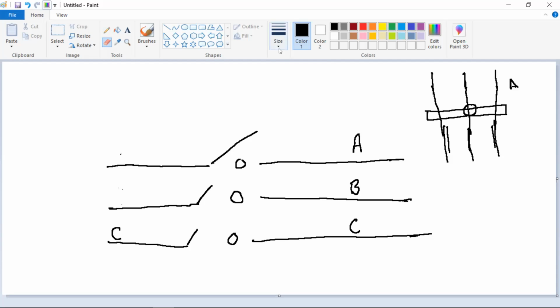So let's go ahead and phase here the way it should be. A, B, C. You should not have to do this because this was previously done at the switch location when it was installed. Now, if you've got questions, or somebody recommends that you phase across this switch just to make sure, maybe it was a very old install or something changed on this feeder circuit over here or over here, and they recommend that you go ahead and do phasing across it.